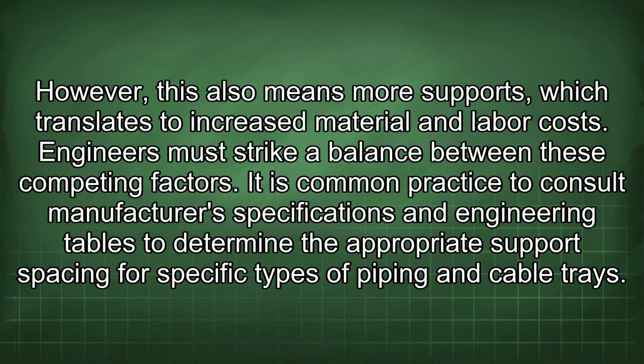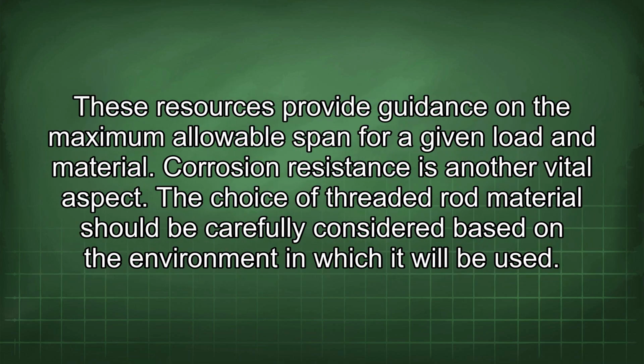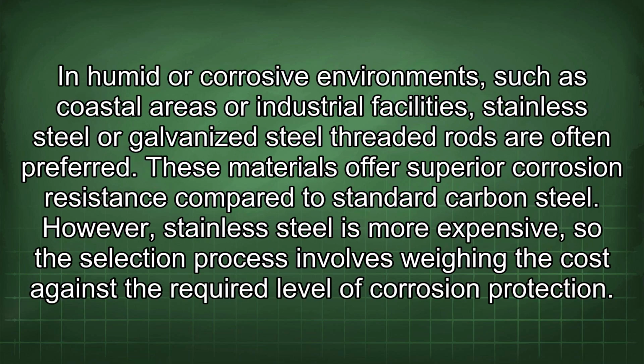It is common practice to consult manufacturers' specifications and engineering tables to determine the appropriate support spacing for specific types of piping and cable trays. These resources provide guidance on the maximum allowable span for a given load and material. Corrosion resistance is another vital aspect. The choice of threaded rod material should be carefully considered based on the environment in which it will be used. In humid or corrosive environments such as coastal areas or industrial facilities, stainless steel or galvanized steel threaded rods are often preferred.